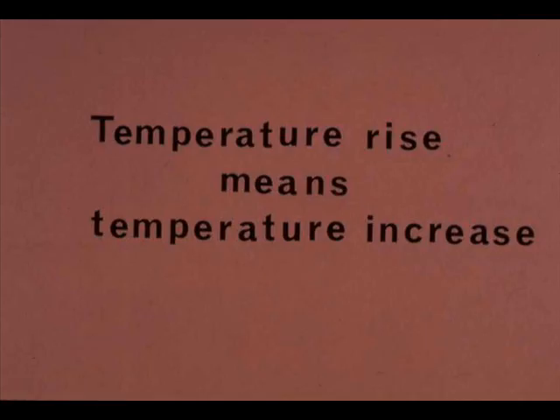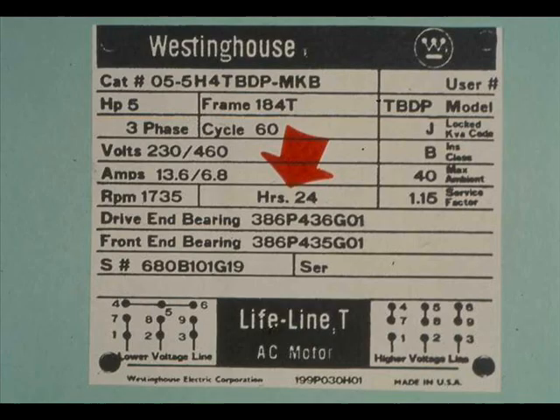Temperature rise means temperature increase, so the manufacturer could have chosen to rate this motor as rise 90 degrees centigrade. The time rating must be stated — that is, the length of time the motor can be run continuously without damage under design conditions. The usual ratings are 5 minutes, 15 minutes, 30 minutes, 60 minutes, and continuous. The time rating for this motor is 24 hours. On some nameplates this rating is listed as 'time'; on others, as 'duty'.